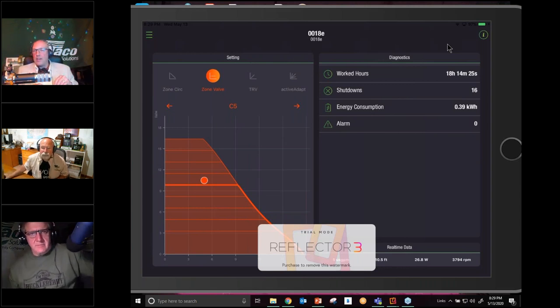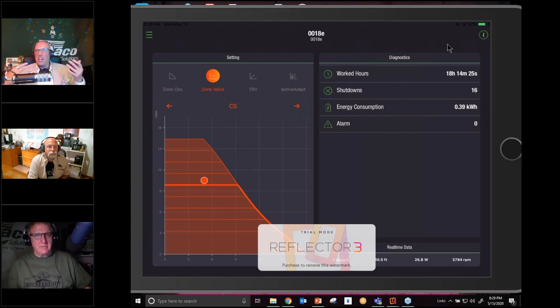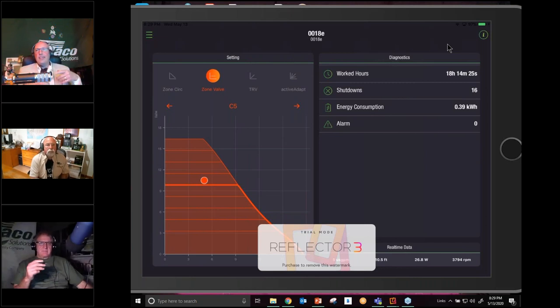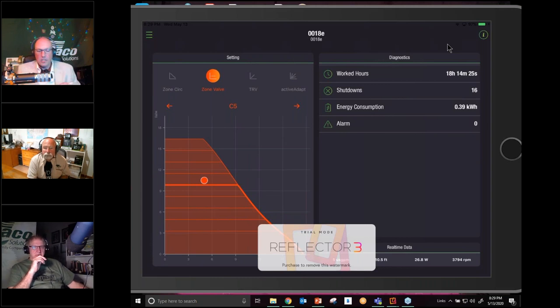You're doing a standard three-way mix valve. Yeah, no, they're not going to. A thermostatic needs to see at least, and a lot of them, especially the radiant ones, about a 27 degree spread between the hot and the mix temperature that you're going to send out there. So you're going to have to jack up the temperature on the boiler itself in order to get that valve to do what it's supposed to do. So if you ever do a modulating boiler or outdoor reset on the boiler side and you've got mixing going on, use a modulating mix valve too. That would be the best way, in what I consider making it do what it's supposed to do. Otherwise, you may compromise that radiant zone and not get the right temperature going out to it.